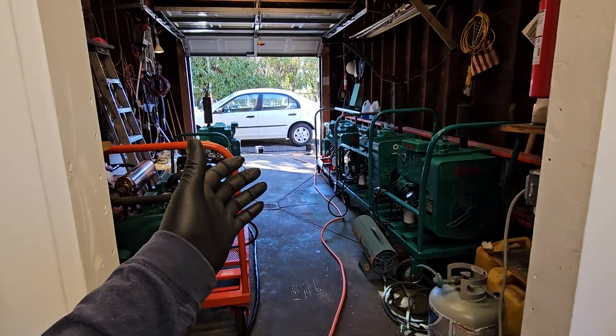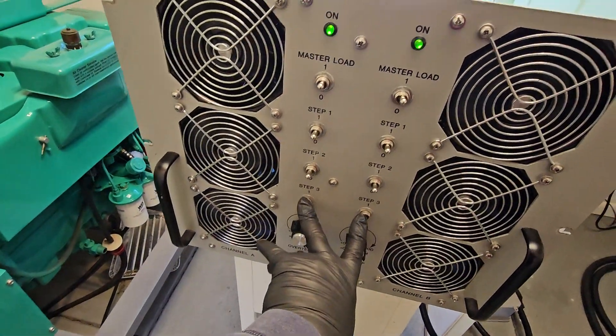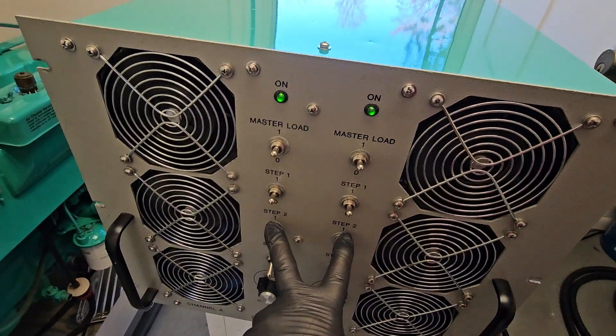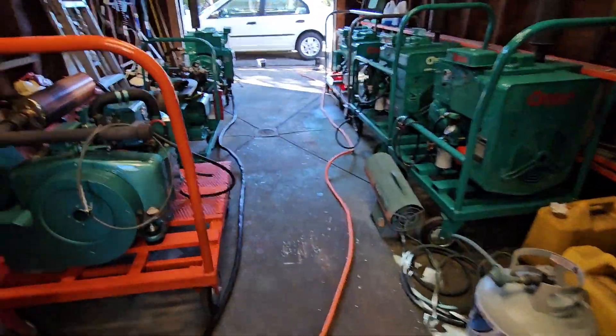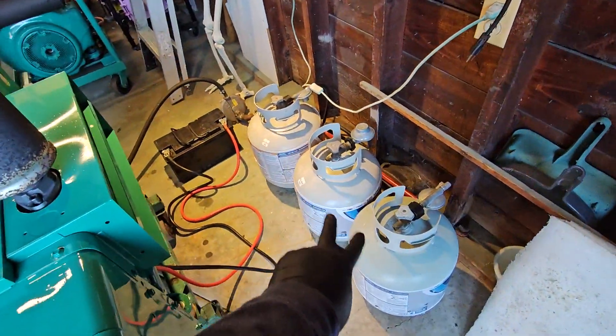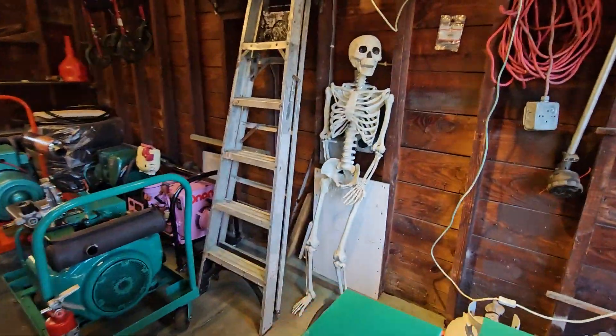Can we let it run for about an hour and watch it blow up? Nah, let's shut it down in steps. We're shutting it down in steps — two steps low. Another two. We should be down to about 4K. 4,500 watts right now, 4,600. Not bad. This is on gaseous fuel, propane. Like I said, we got three tanks here. She's running good.